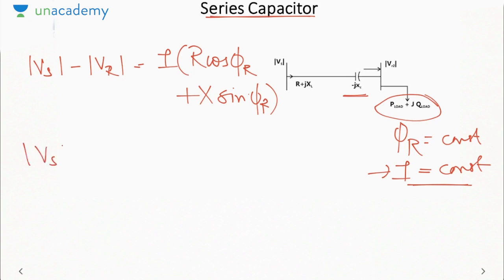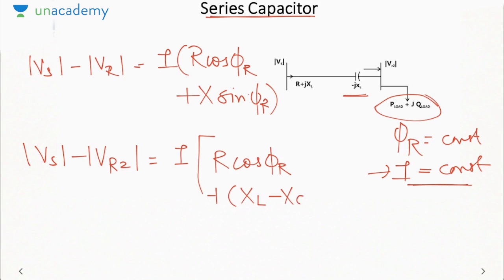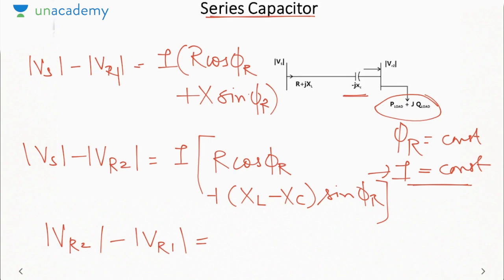And after connection, what will be mod Vs minus mod Vr2? It will be I R cos phi r plus XL minus XC sin phi r. This will be the voltage drop. So if we subtract the two equations, mod Vr2 minus mod Vr1, let us call this as mod Vr1, it will come out to be I into XC sin phi r. Okay, so it is greater than 0. Hence, series capacitor also increases the receiving end voltage by reducing the voltage drop in the transmission line.